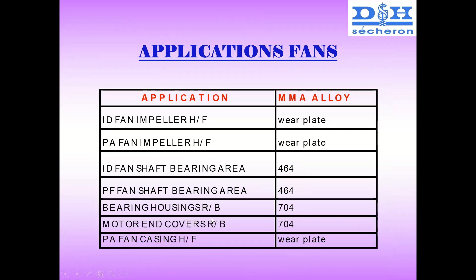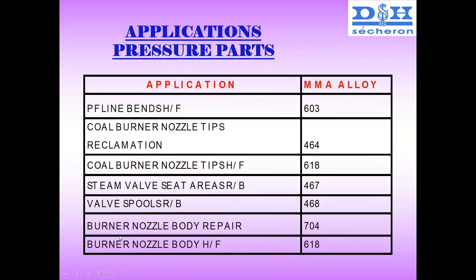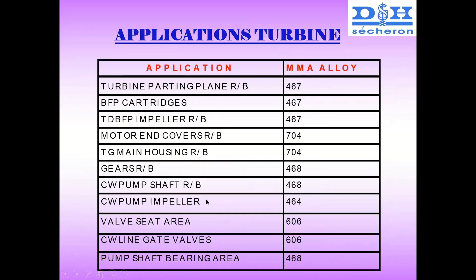We have seen a lot of fans where the fan impeller gets worn out. The best option is to put a wear plate on it, and we have supplied wear plates to fan applications in power plants. Pressure part coal burner nozzle tips hard facing is a very common application. Burner nozzle body repair and hard facing are also available. For turbine valve seat areas, the application normally uses stellite, and we have stellite available in both conventional and other ranges.